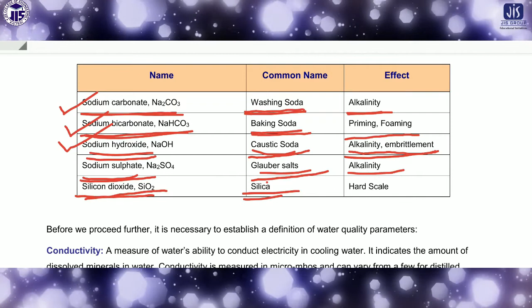So here also there are some compounds, like sodium carbonate, sodium bicarbonate and sodium hydroxide. These all create alkalinity or foaming. And one important thing is that silicon dioxide, SiO2, is present, which is also responsible for the hard scale. Okay, hard scale is very dangerous, because I told you that when hard scale is produced, the heat distribution will not be uniform, or at one level. So if the heat distribution is not the same, there is a high chance of cracking in the scale, and there may be some kind of explosion also possible there. So first of all, it is the main thing which we have to control. This is the scale generation.